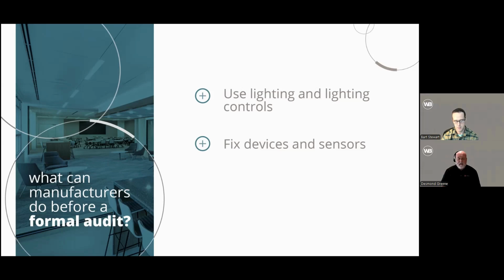Fix devices and sensors. Again, that goes back to the retrocommissioning that Bart talked about. You fix, replace, or repair existing devices that you identify as not working. You may have them in your maintenance logs, and you haven't got around to them yet. We highly recommend that you do that, because things like steam traps, if they're leaking by, can cost an awful lot of money. Motorized dampers, valve actuators, sensors. If you know that they're not working or they should be recalibrated, fix them, recalibrate them, or replace them.